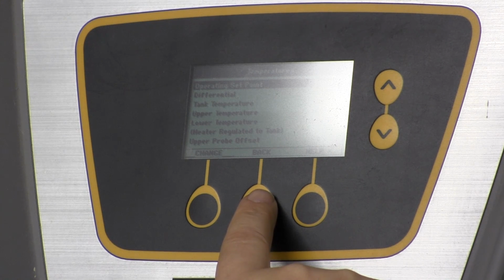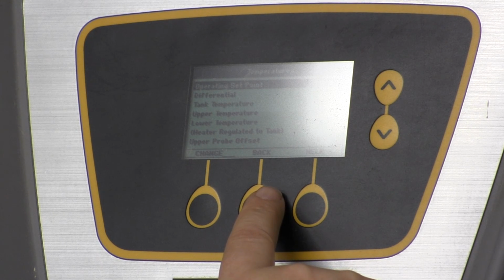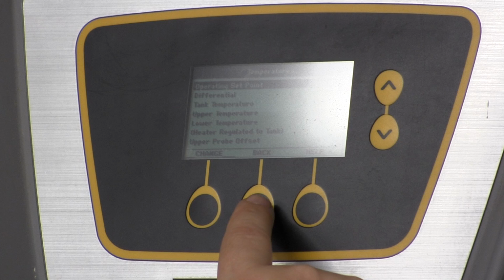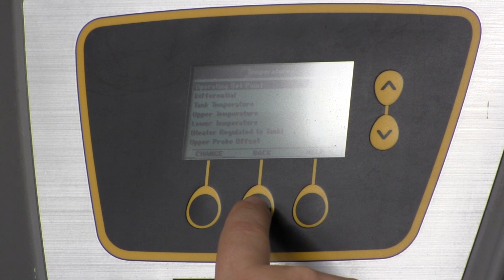Yeah, 20 degrees. You want to keep them in the condensing range if you can. And what is the condensing range on these guys? They'll condense from anything above room temperature, so from 90 to 140. So that's part of the 142. Yeah, it's within its condensing range. If we did put a booster in the kitchen, we could keep these at 120. In theory, yeah. And would they?